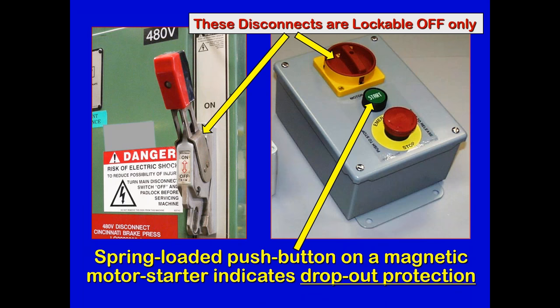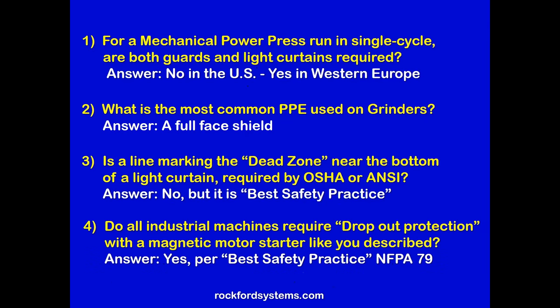So on the left, you need a disconnect switch you can padlock in the off position. It's a flange-type disconnect where the handle goes up and down, and yes, it's lockable only off. On the right, you've got a rotary-type disconnect that's also lockable only in the off position. Notice the start button underneath that? That's a symbol of a magnetic motor starter because the push button is spring-loaded, as opposed to that old mechanical switch that we saw on the engine lathe. There's also a red emergency stop button, as you can see. So this stuff comes out of NFPA 79.